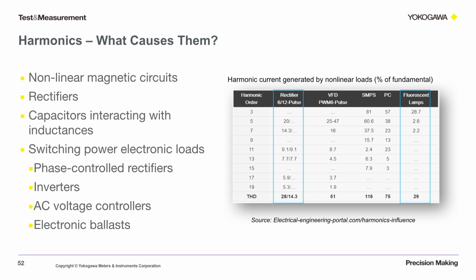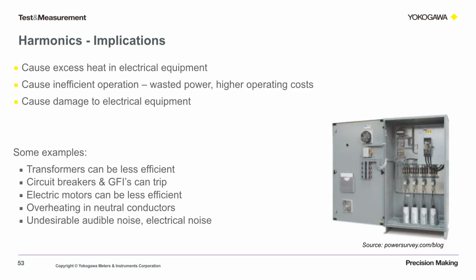So in our two examples, the rectifier circuit, like the one in our AC drive, we can have a contribution of 20% harmonic current in the fifth harmonic. And using the fluorescent light example, we can have 29% current within the third harmonic. Because harmonics can cause excess heat, wasted power, and potential damage to our equipment, we want to be able to accurately measure them so we can both understand what's present and help us reduce them. The reduction of harmonics is another topic outside of this webinar.